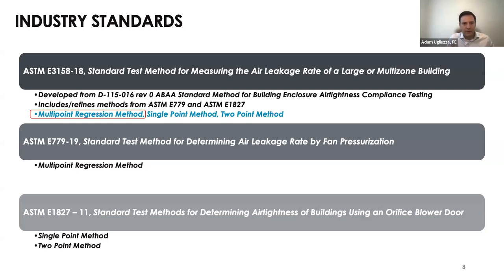So what we did with 3158 was basically combine those. So you have the multi-point, the single point, and the two point methods all in one standard. And then we also provided more guidance as to how to actually perform the test. 779 and 1827 were limited in direction, and because of that, there were some issues with repeatability and accuracy of the testing. With 3158, the goal was to correct those issues so that we could get more repeatable and more accurate testing as we roll this out across the country and we're testing millions of buildings.